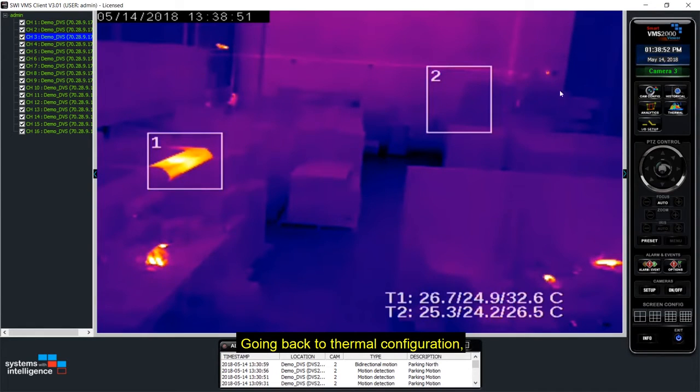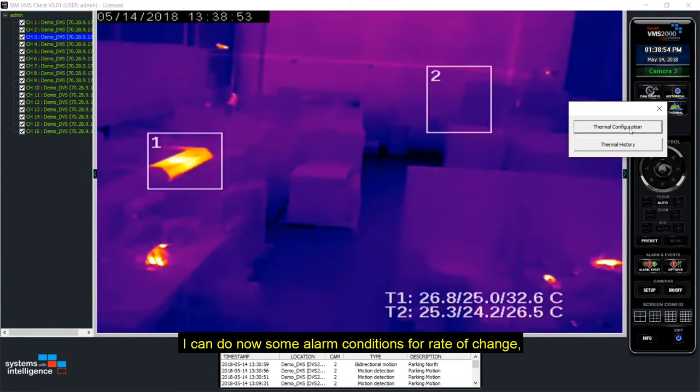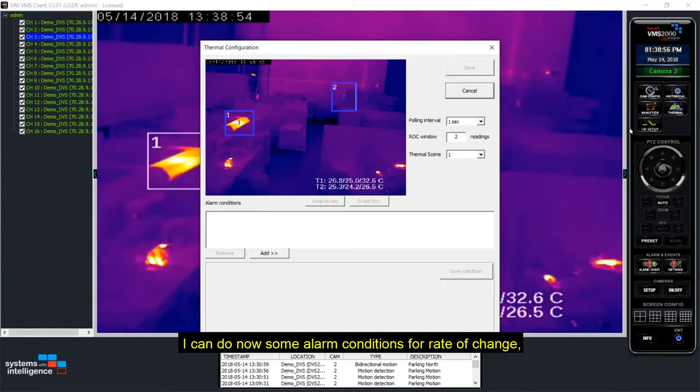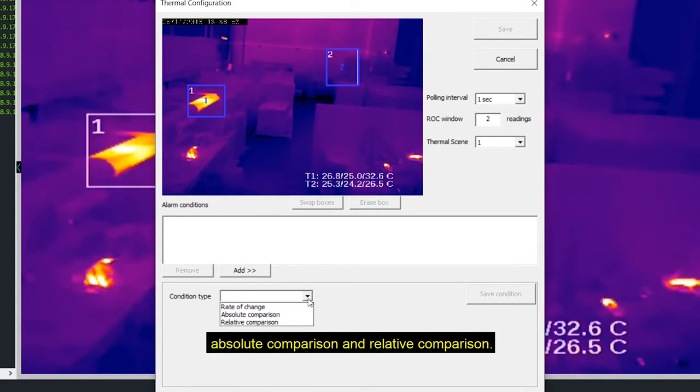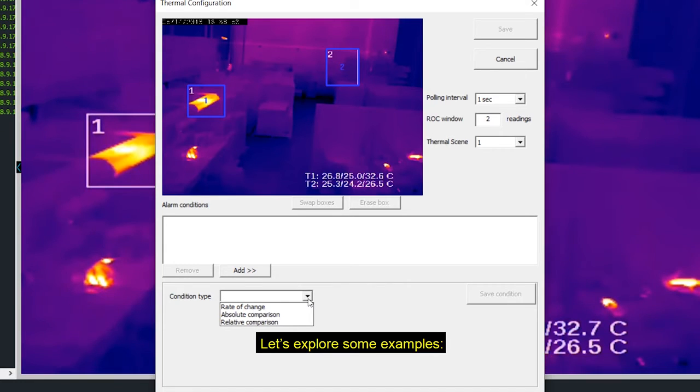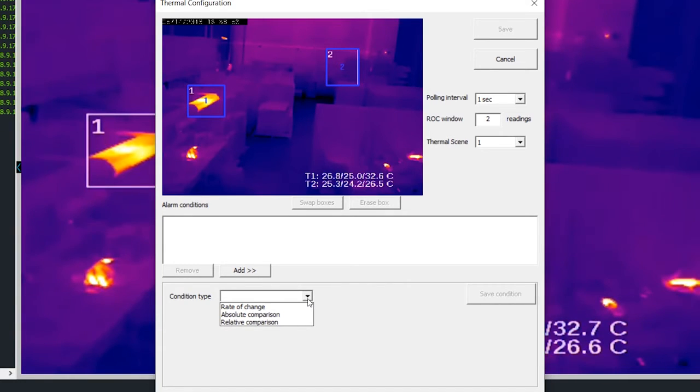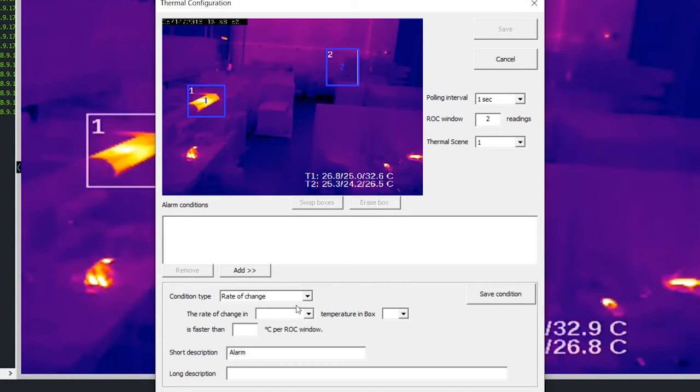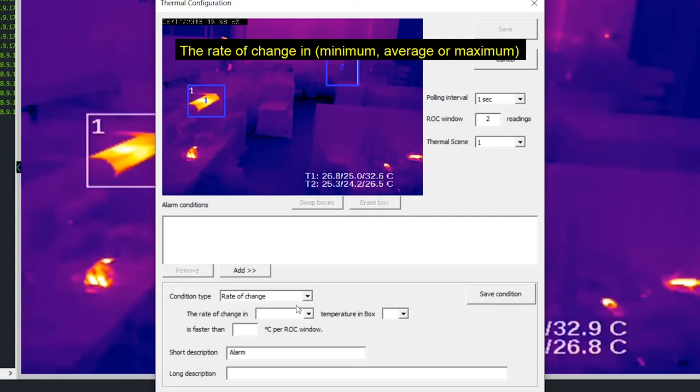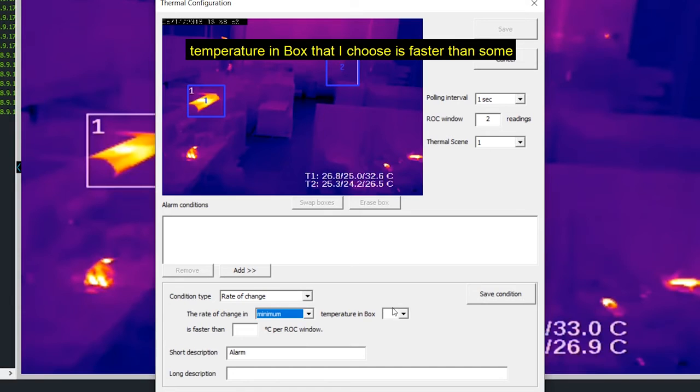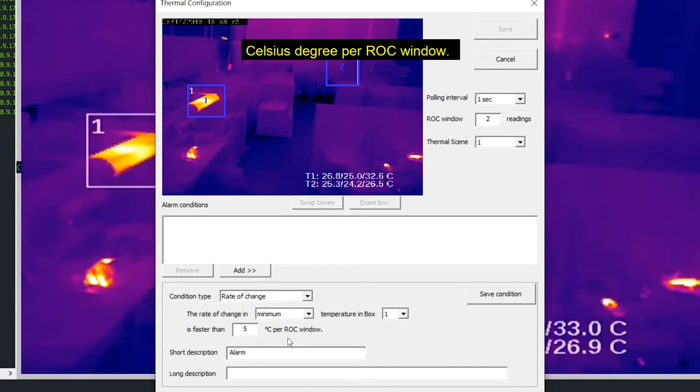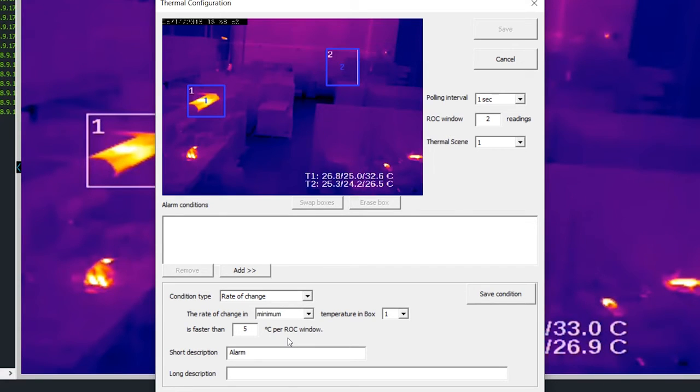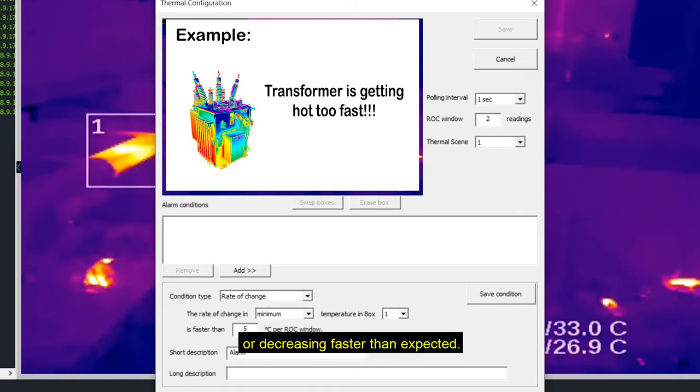Going back to thermal configuration I can do now some alarm conditions for rate of change, absolute comparison and relative comparison. Let's explore some examples. Condition type, rate of change. The rate of change in minimum, average or maximum temperature in box that I choose is faster than some Celsius degree per ROC window. We use this rule when we want to check if the temperature is increasing or decreasing faster than expect.